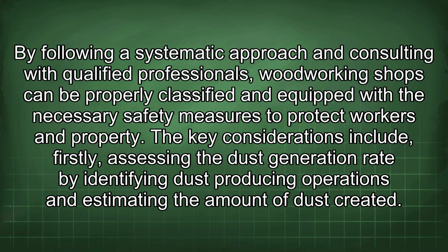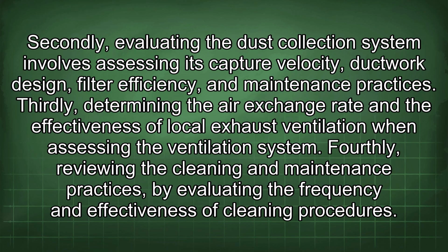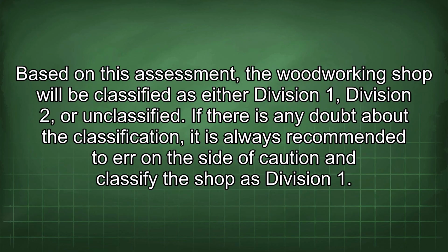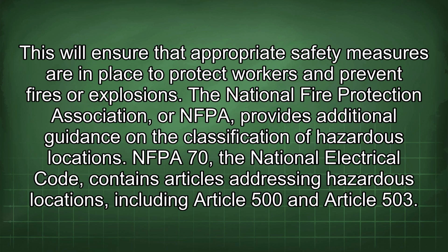The key considerations include: firstly, assessing the dust generation rate by identifying dust-producing operations and estimating the amount of dust created. Secondly, evaluating the dust collection system involves assessing its capture velocity, ductwork design, filter efficiency, and maintenance practices. Thirdly, determining the air exchange rate and the effectiveness of local exhaust ventilation when assessing the ventilation system. Fourthly, reviewing the cleaning and maintenance practices by evaluating the frequency and effectiveness of cleaning procedures. Based on this assessment, the woodworking shop will be classified as either Division 1, Division 2, or unclassified. If there is any doubt about the classification, it is always recommended to err on the side of caution and classify the shop as Division 1. This will ensure that appropriate safety measures are in place to protect workers and prevent fires or explosions.